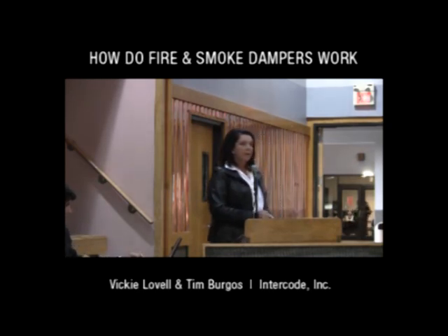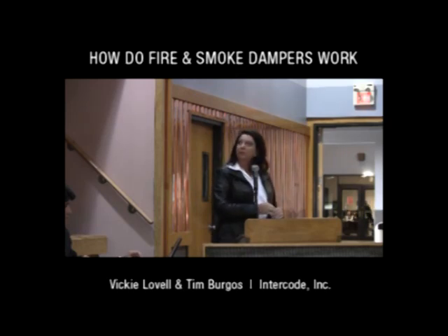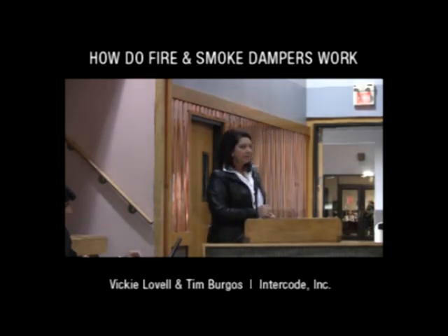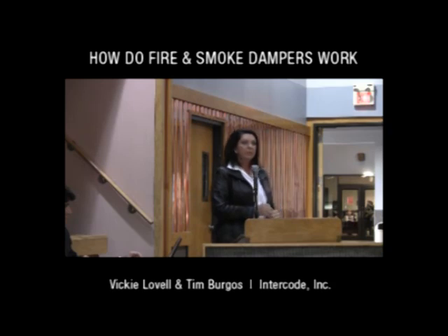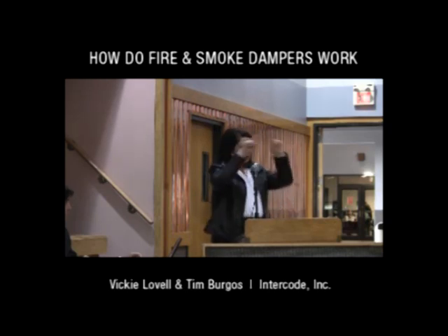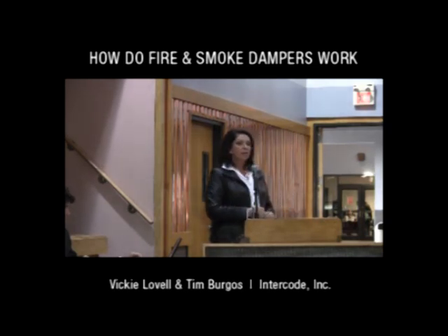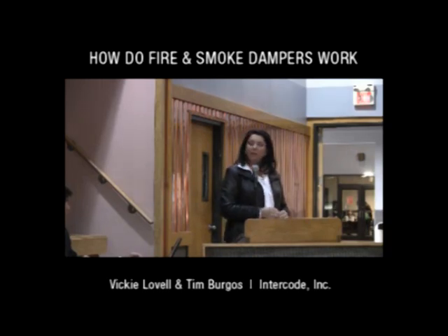Fire-rated walls in particular are intended to provide compartmentation from one room to another room. Sometimes they're intended to protect the structural elements of a building. But in any case, where compartmentation is the function of a fire-rated wall, if smoke or the byproducts of fire, toxic gases, hot gases pass through the HVAC system into the next compartment, then the people that are remote from the fire now are in danger. And the intent of the fire damper and the smoke damper, combination fire smoke damper, is to close that opening within the duct itself, and also the retaining angles around the duct are intended to close off any openings that would allow fire smoke to.